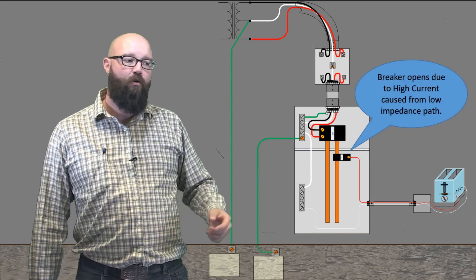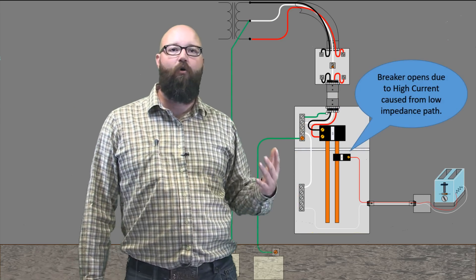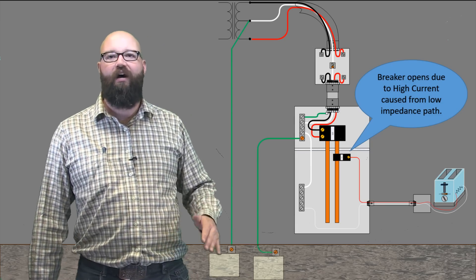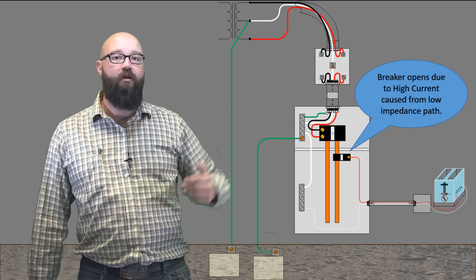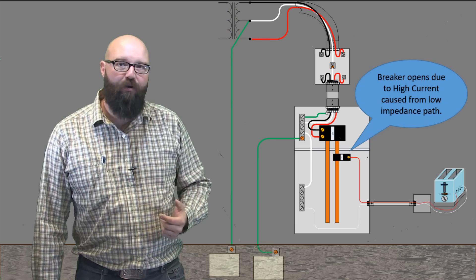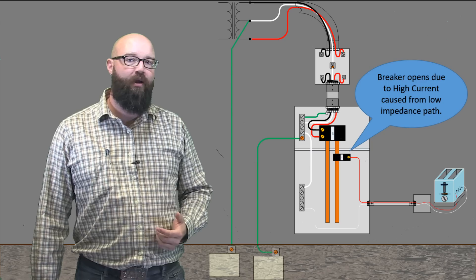Why did it open the breaker? Well, because we have this low impedance path. And we know Ohm's law tells us that if I have a very low impedance, I end up with a very high current. And we use that very high current to trip the magnetic portion of that breaker.